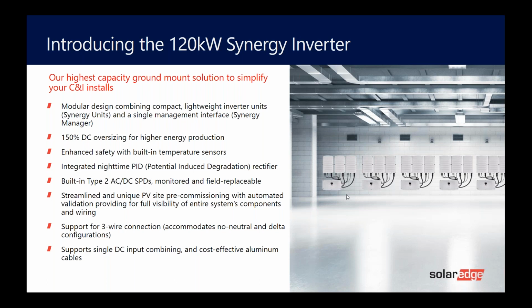That's very exciting. Built-in Type 2 AC and DC surge protection. Everybody has code-required surge protection on the AC side, but we've added additional surge protection on both the AC and DC side that's field replaceable and monitored. So if there's a lightning strike or a surge, you'll be notified and can go out and replace it. That's something worth talking about too.